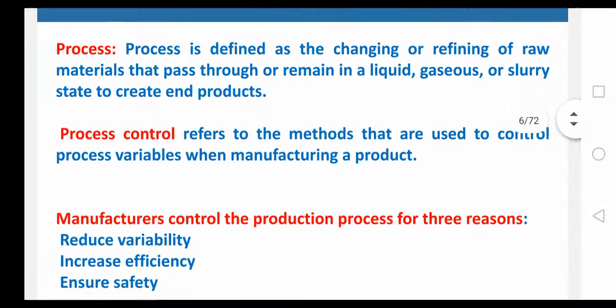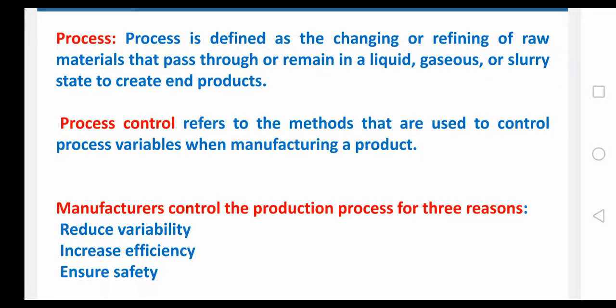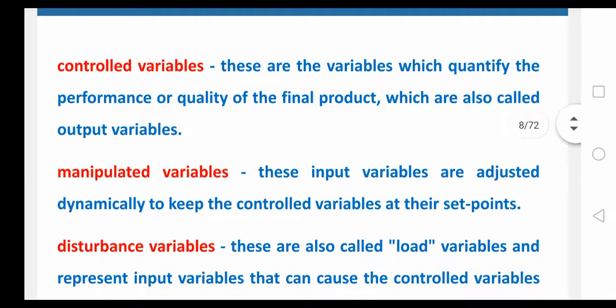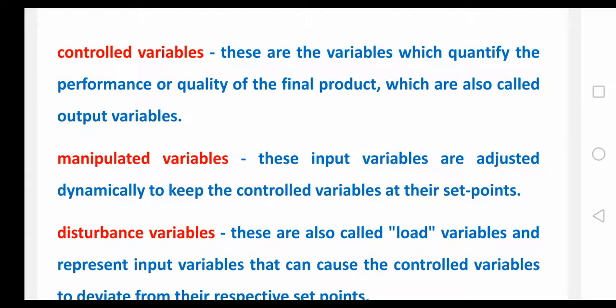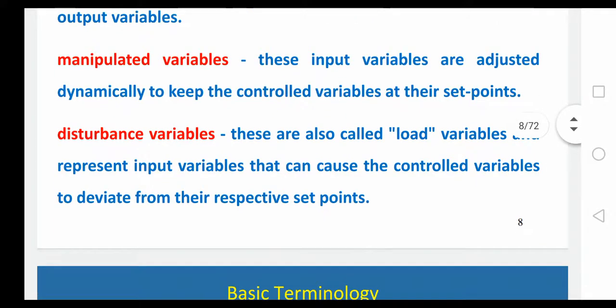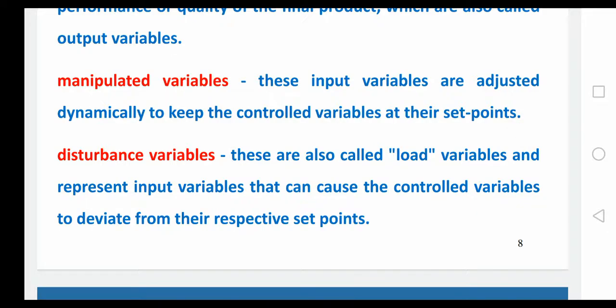Process control — what is process control means — it refers to the methods that are used to control process variables when manufacturing a product. Manufacturers require: reduce the variability, increase efficiency, ensure safety. And control variables — these are the variables which quantify the performance or quality of the final product, which are also called output variables. Manipulated variables — these input variables are adjusted dynamically to keep control variables at their set points. Disturbance variables — also called load variables — represent input variables that can cause the control variables to deviate from their respective set points.